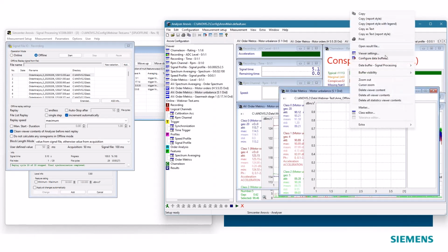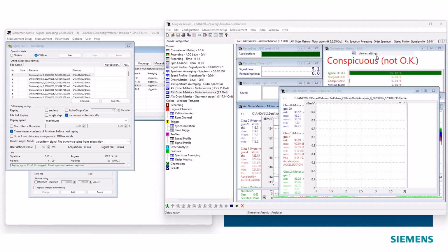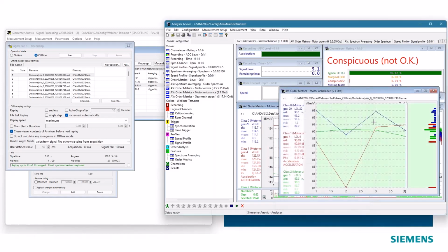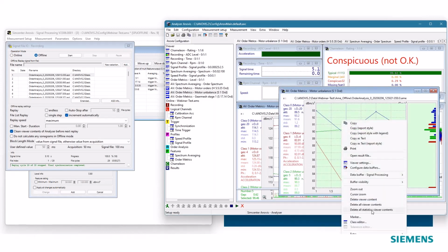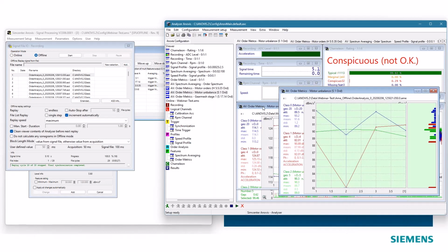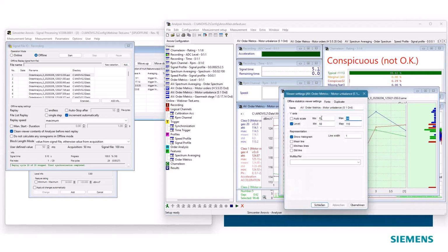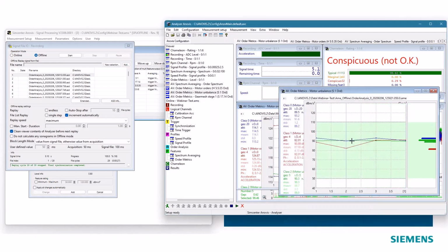So here is the same view settings, auto plus level. So you see a trend, plus you see a histogram on the right. Exactly. Right is the histogram, and here you see a trend. Maybe I have to zoom out. However, if you look at the settings, let's put this to 130 and this to, let's say, 40. You see for the order metrics, for the unbalance and also for the gear metric, there's no difference between motor orders and not motor order issue.